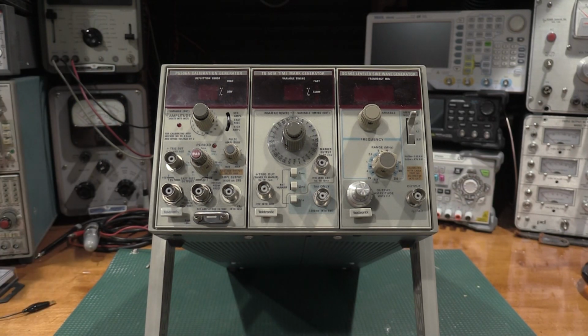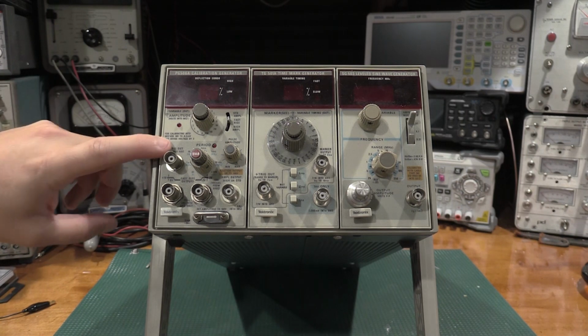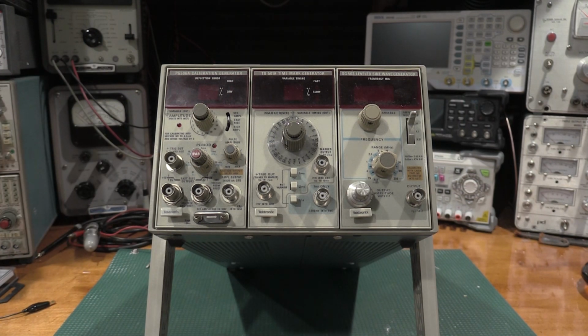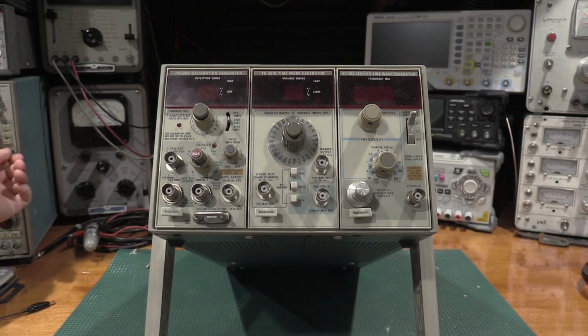Those high current transistors in some of the frames do tend to blow. When they do blow, they can take plugins out, because one of the main things they do is act as pass elements for the voltage regulators of the plugins - depending on the plug-in. So when those are shorted, it's not a good day. Let's power up the frame, and then we'll sanity check the plugins, make sure they're doing what they're supposed to be doing and giving us sane output, and then we'll check deeper.